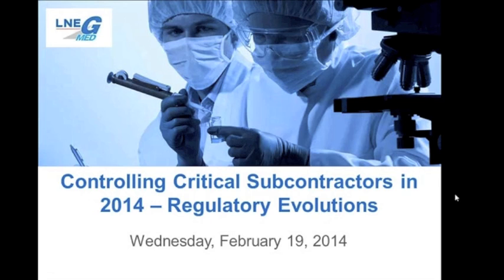As you all probably already know, the European Medical Device Regulatory Scheme is currently being rewritten. It's in the middle of the EU legislative procedures right now, and even more changes are expected before we have a final text. However, we already know that some points will survive the different legislative bodies' scrutiny, and one of those is the way that notified bodies audit manufacturers with respect to how manufacturers control their critical subcontractors.